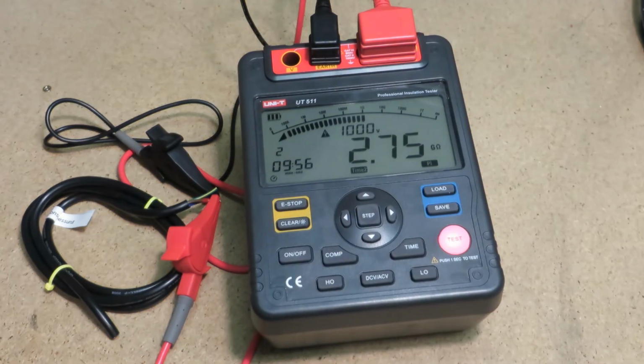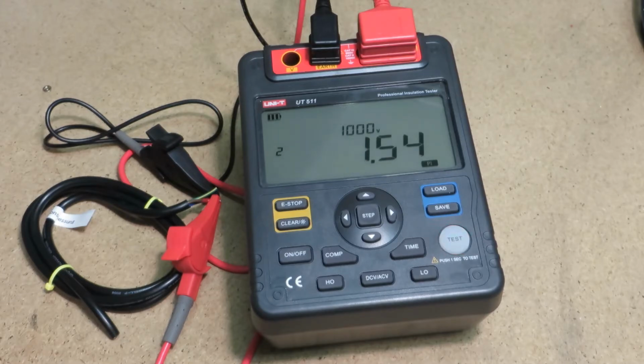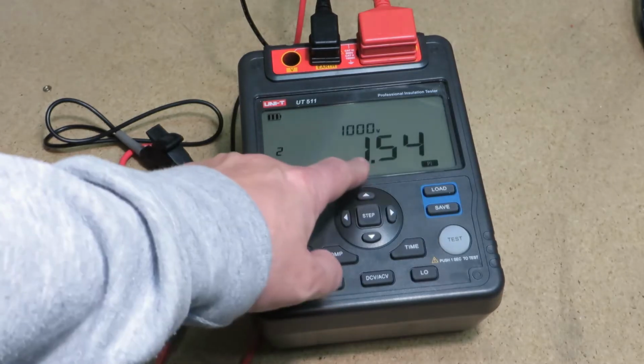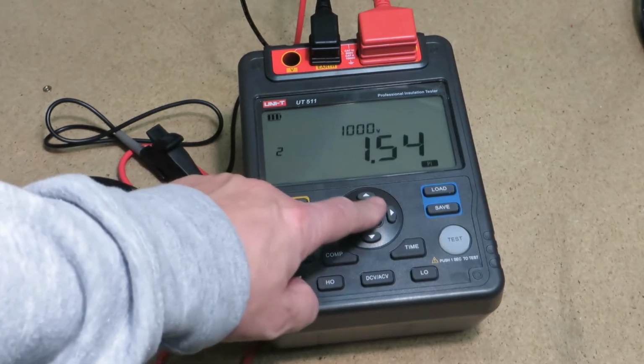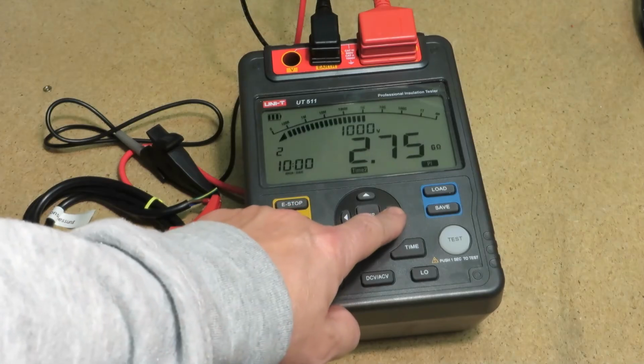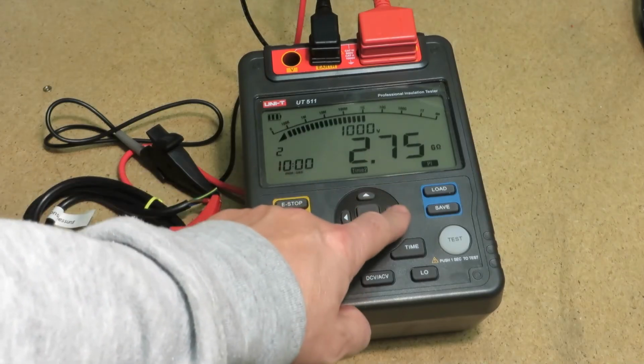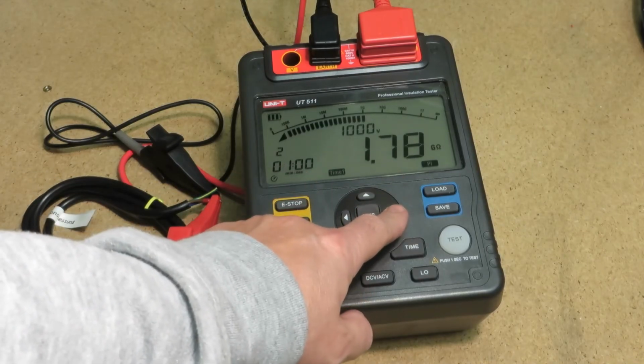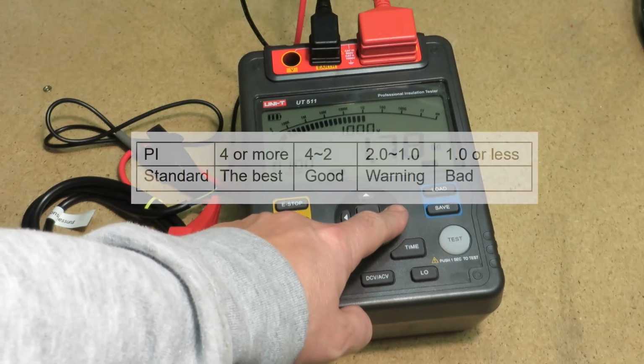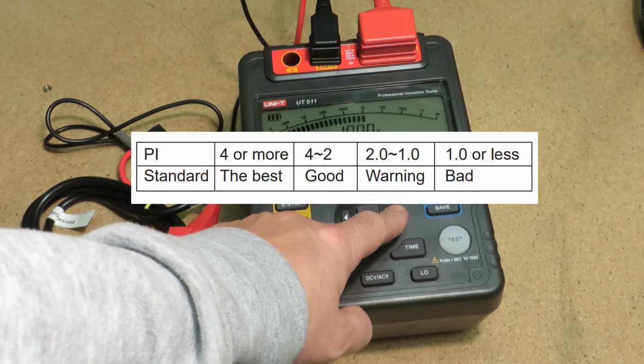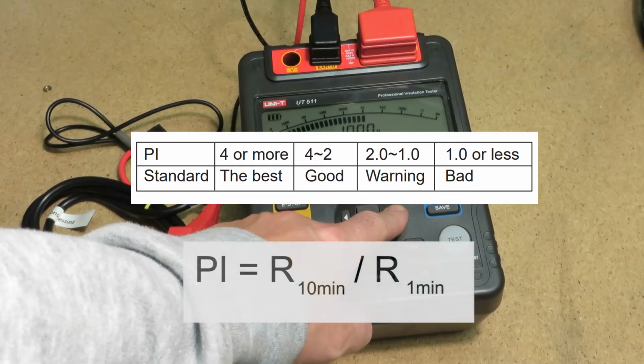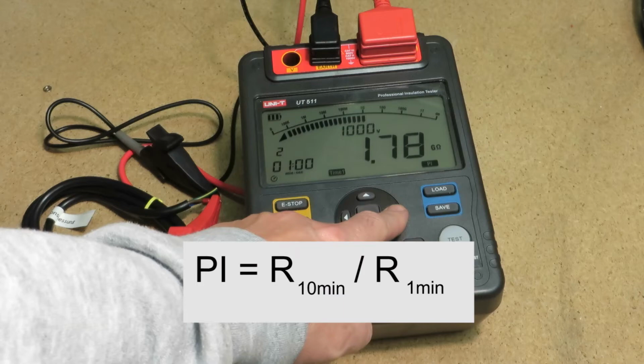After 10 minutes, timer 2 stops and finished the measurement. The display shows the calculated Pi value of 1.54. By pressing arrow right, it shows the resistance value after 10 minutes, and another right press shows the value after 1 minute. This table shows the meaning of the Pi values. The Pi value is calculated by resistance value after 10 minutes divided by the value after 1 minute.